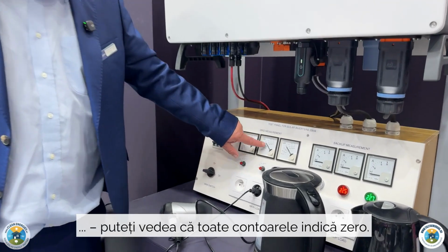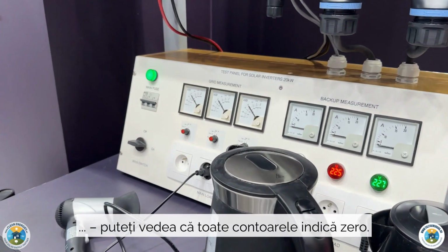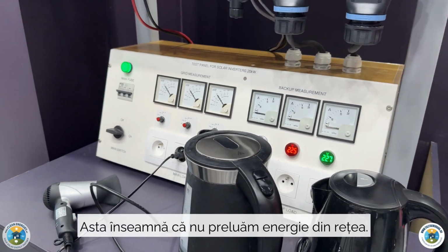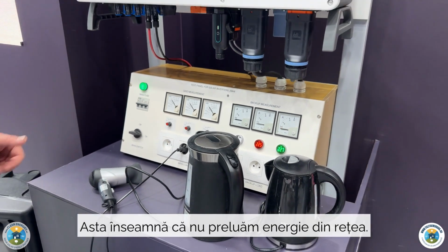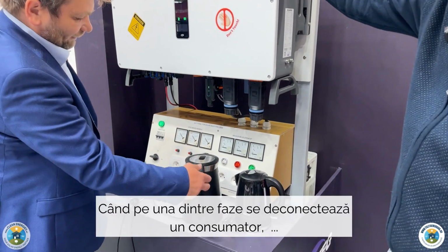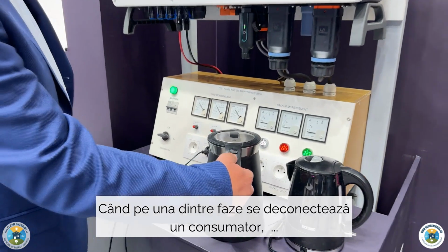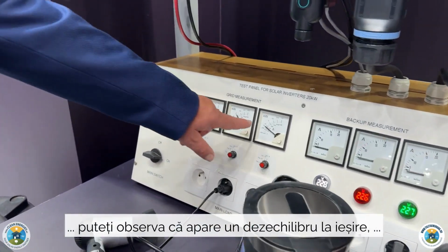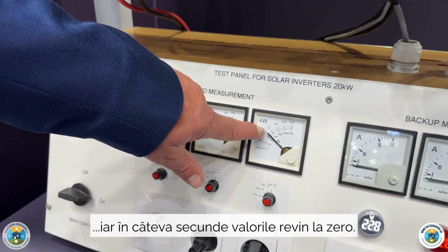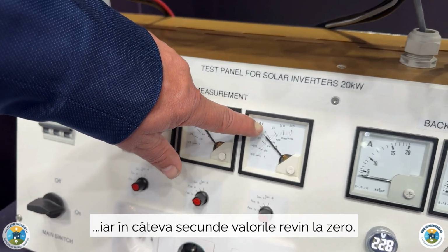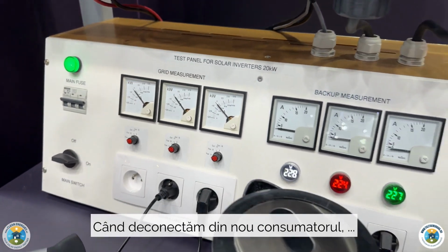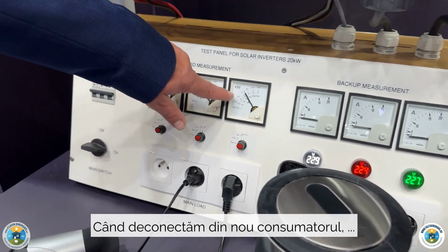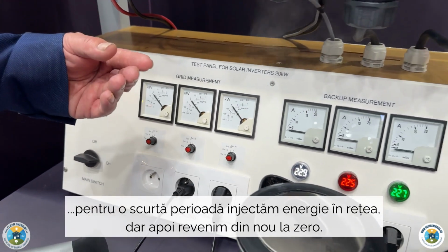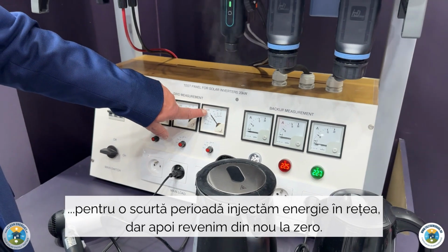You see all the wattmeters are on zero, meaning we're taking zero electricity from the grid. When we switch off some load on one phase, you see now we have some unbalanced output, and in a couple of seconds it goes back to zero. When we switch off the load again, we briefly feed power to the grid, but then we get back to zero.